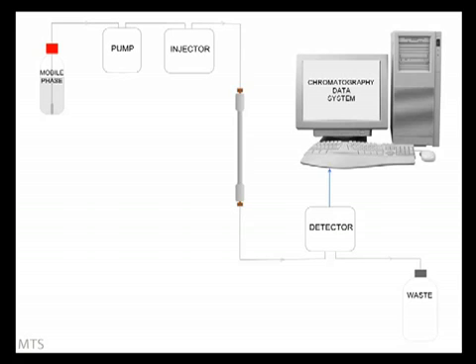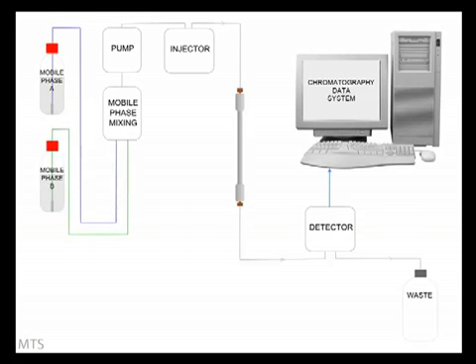In gradient analysis, the composition of the mobile phase is changed during the course of the analysis. To enable this we need another mobile phase reservoir and some way of mixing the two. The mixing may be performed before the pump as shown here, in which case it is not yet under pressure and is called low pressure mixing.